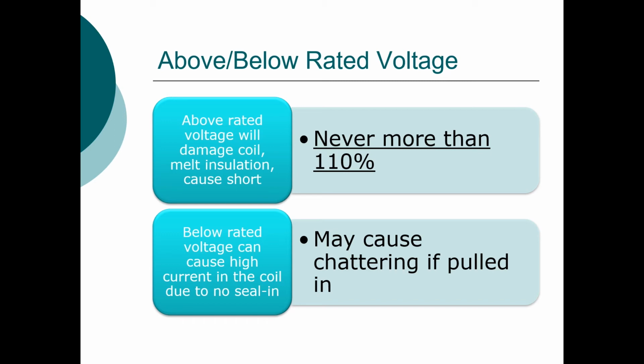High voltage across a coil could have two different dangerous effects. First, it could cause the armature to snap into place too quickly, which will damage the internal components of the relay. Or, the high voltage causes a high current, which will cause excessive heat, which will break down the insulation and cause an internal short. The coil voltage should never be more than 110% of the rated voltage.